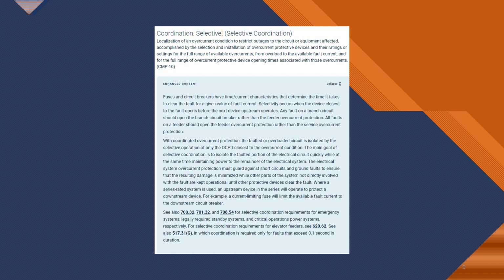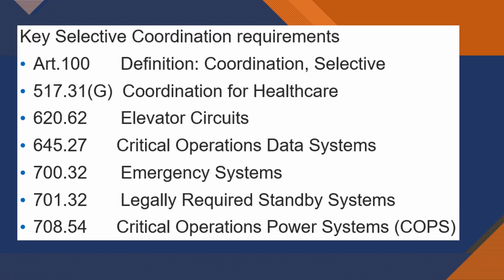So our overcurrent condition is what? Overload, short circuit, or ground fault, right? Most likely we're going to be talking about a short circuit or a serious ground fault in order to make selective coordination required or important.